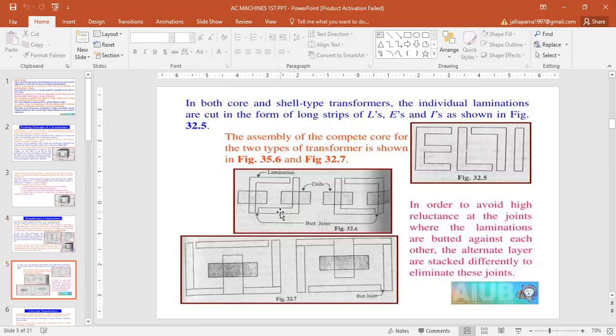In both core and shell type transformers, the individual laminations are cut in the form of long strips of L's, E's, and I's, as shown in the figure. The assembly of the complete core of the two types of transformer is shown in the figure. In order to avoid high reluctance at the joints where the laminations are butted against each other, the alternate layers are stacked differently to eliminate these joints.